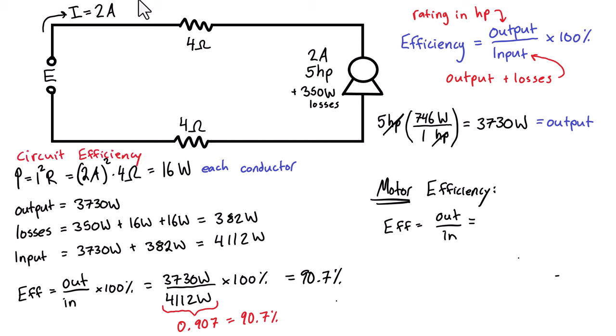So for the motor itself, it's putting out 3730 watts. But for the input to the motor, what's going into the motor is the output of the motor plus the losses of the motor. So it's going to be over 3730 watts plus that 350 watts. You can't consider those 16 watts that are getting lost in each conductor to be going into the motor because they're not going in, they're getting lost in the rest of the circuit.